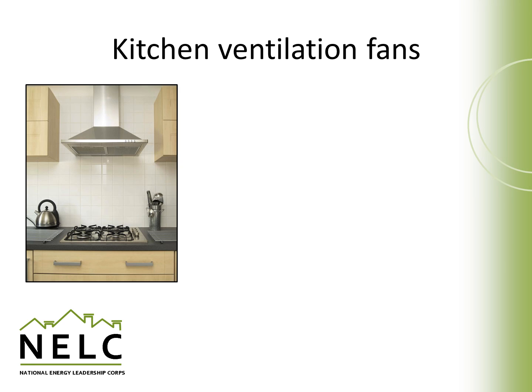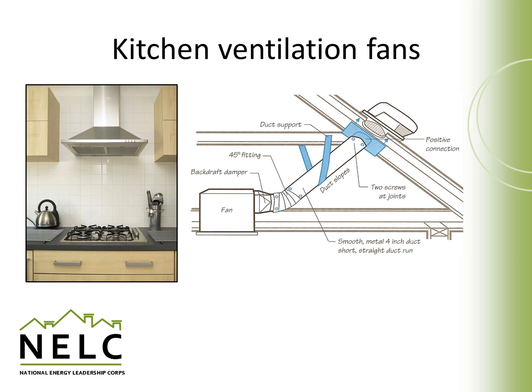Kitchen ventilation fans are fairly common. They can exhaust moisture as well as fumes being introduced in the kitchen. These should also be installed according to recommended instructions. Smooth ductwork with turns that aren't too sharp can make sure they don't get clogged and that they work properly. A backflow damper is an important piece of this type of fan because it will reduce the amount of natural heat flow and air loss through the fan unit when it's not running.